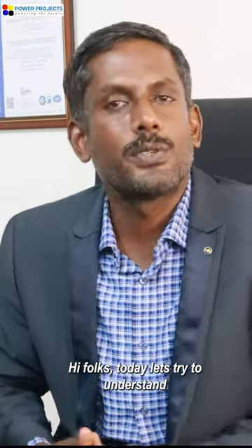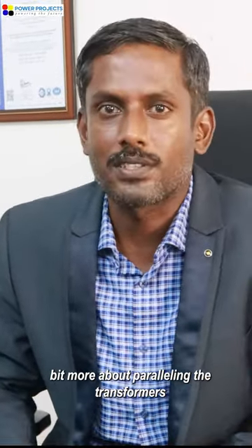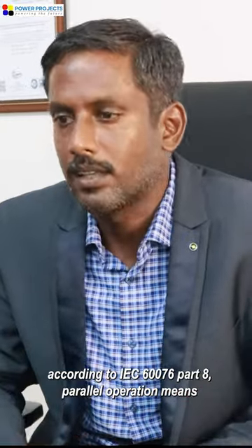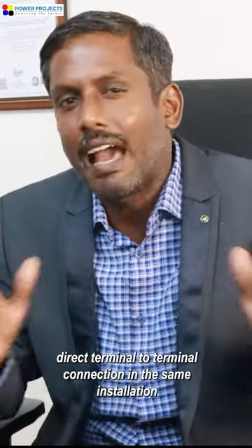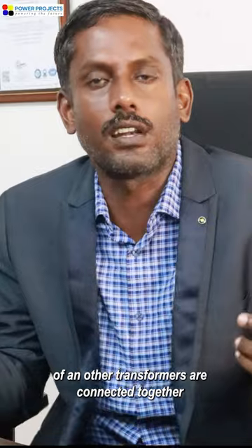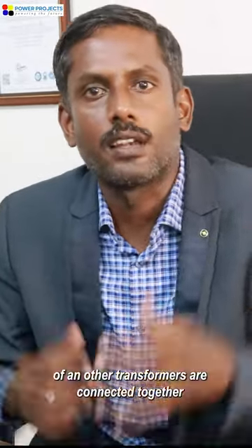Hi folks, today let's try to understand a bit more about paralleling the transformers. Let's ask the first question. What is paralleling of transformers? According to IEC 60076 Part 8, parallel operation means direct terminal to terminal connection in the same installations. That means transformer HV and HV of another transformer are connected together. Transformer LV and LV of another transformer are connected together.